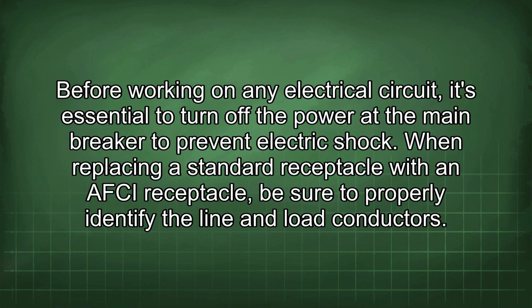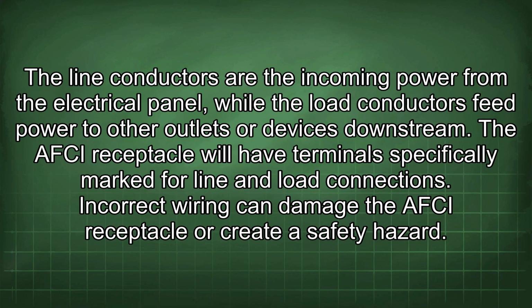Before working on any electrical circuit, it's essential to turn off the power at the main breaker to prevent electric shock. When replacing a standard receptacle with an AFCI receptacle, be sure to properly identify the line and load conductors. The line conductors are the incoming power from the electrical panel, while the load conductors feed power to other outlets or devices downstream. The AFCI receptacle will have terminals specifically marked for line and load connections. Incorrect wiring can damage the AFCI receptacle or create a safety hazard.